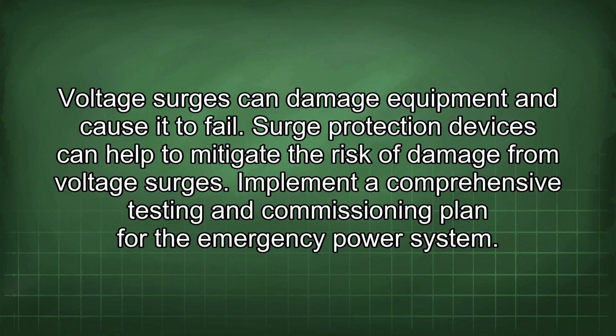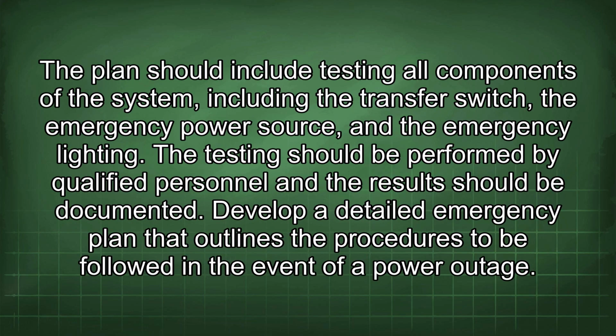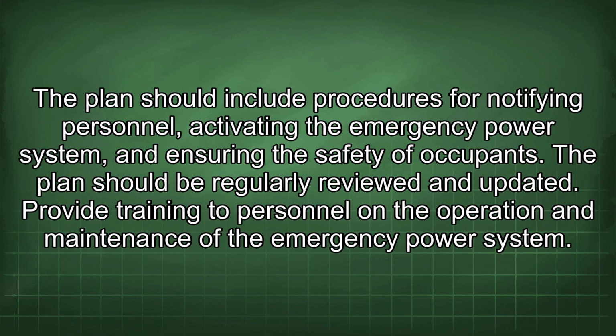Implement a comprehensive testing and commissioning plan for the emergency power system. The plan should include testing all components of the system, including the transfer switch, the emergency power source, and the emergency lighting. The testing should be performed by qualified personnel and the results should be documented. Develop a detailed emergency plan that outlines the procedures to be followed in the event of a power outage. The plan should include procedures for notifying personnel, activating the emergency power system, and ensuring the safety of occupants. The plan should be regularly reviewed and updated.